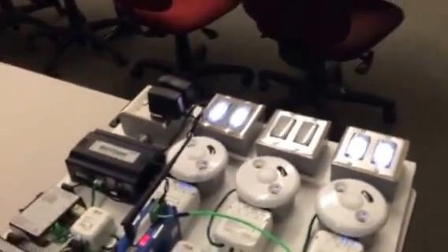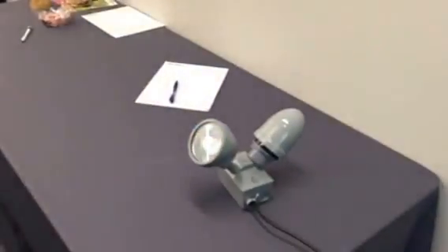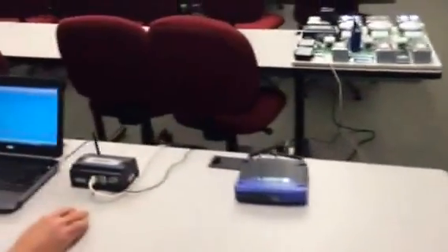What really starts to get interesting for us is that Elliot can also use that same interface to control wireless DLM products. And so Elliot, what I'd like for you to do is control pole number 3 in our parking lot. Just manually turn it on and turn it off. So he has control of that, and then when he's turning that on, we also get some really good information about that load. So this is all he's doing. Activating it on and off takes just a couple of seconds for the information to come up. And what you're going to see is that the amps, the watts, and the volts specific to that load are all being shown up.